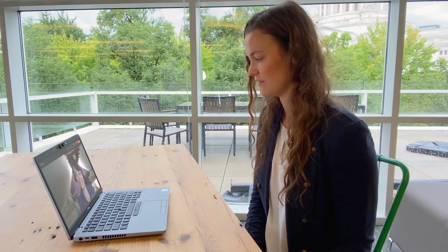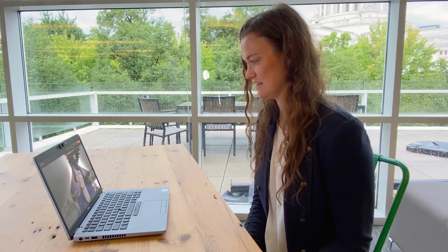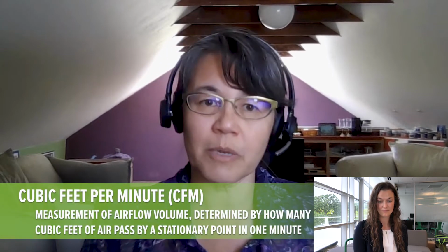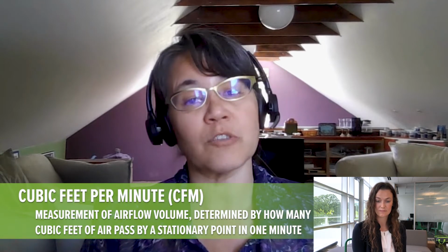How do I know that the ERV is sized correctly for my house? So let's start with the design. The best design for balanced ventilation is continuous low volume ventilation. But you should also be able to increase the ventilation flow when you've taken a shower or when you're cooking or when you have guests. So the right size ventilator is big enough to boost to high speed, but the controls should also allow low speed operation. Just for sizing purposes, you can think of about 50 CFM, which means cubic feet per minute of air. 50 CFM per bedroom is a good way to start thinking about size. Though a small home could get away with less, and a large home would need more air, regardless of how many bedrooms there are. Got it.